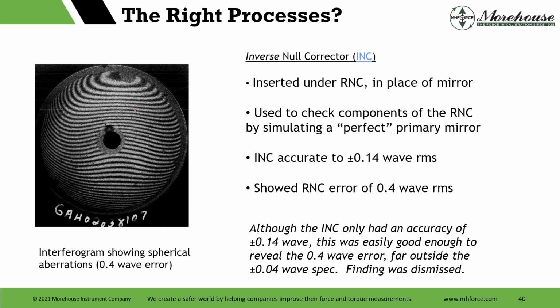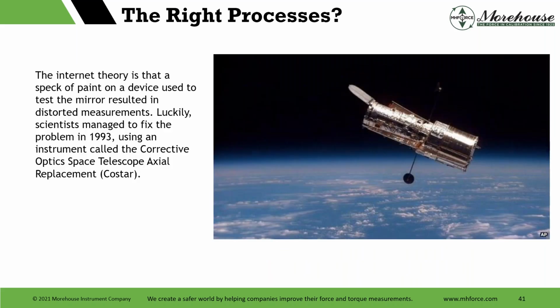So you had spherical aberration, a 0.4 wave error, and although the INC only had an accuracy of 0.14, talking about ratios, about 3 to 1, a little worse than that, this was easily good enough to reveal the 0.4 wave error, far outside the 0.04 wave spec. The finding was dismissed. Measure something, don't like it, do it again, let's go with the RNC, send it up into orbit, it doesn't focus.